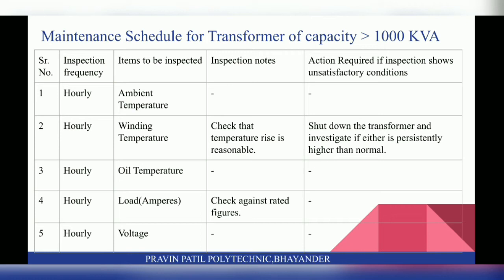Next is the Maintenance Schedule for transformers of capacity greater than 1000 KVA. On an hourly basis, check ambient temperature and winding temperature. Ensure the temperature rise is reasonable. Shut down the transformer and investigate if either is persistently higher than normal. Also check oil temperature and load in amperes — check against rated figures. Additionally check voltage against rated figures.